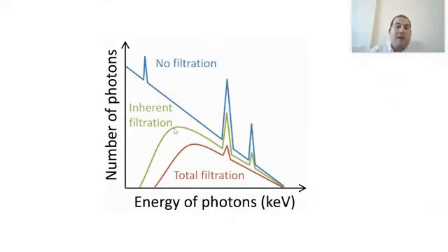Beam hardening is the same concept we are discussing, where the X-ray beam itself is filtered by the patient before encountering a high-density material. What happens is that it removes all the soft energies, all the weak energies, which increases the average energy and thus increases the penetration power of the X-ray passing through the slice. Consequently, when it reaches the detector, the detector does not understand what to do. It starts observing the X-ray photons that have reached it and begins to perform normalization.